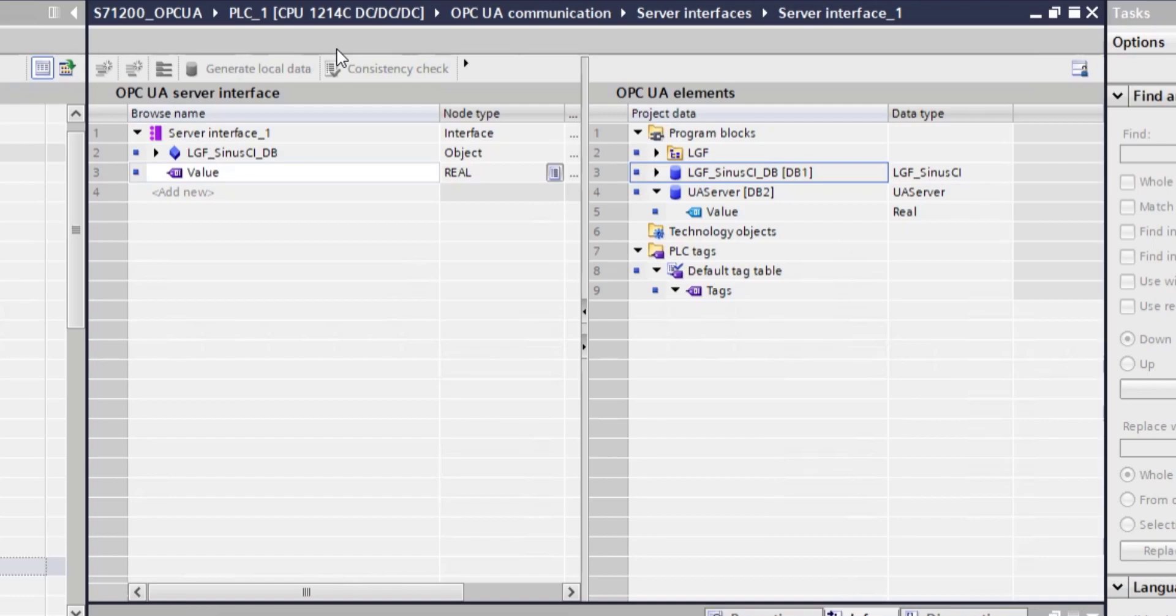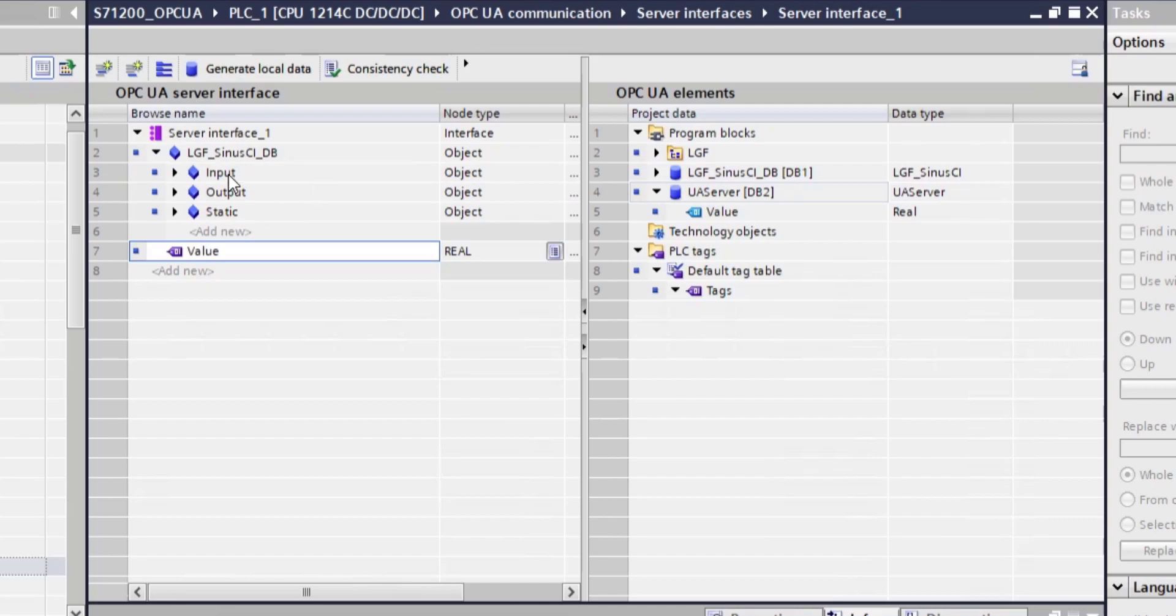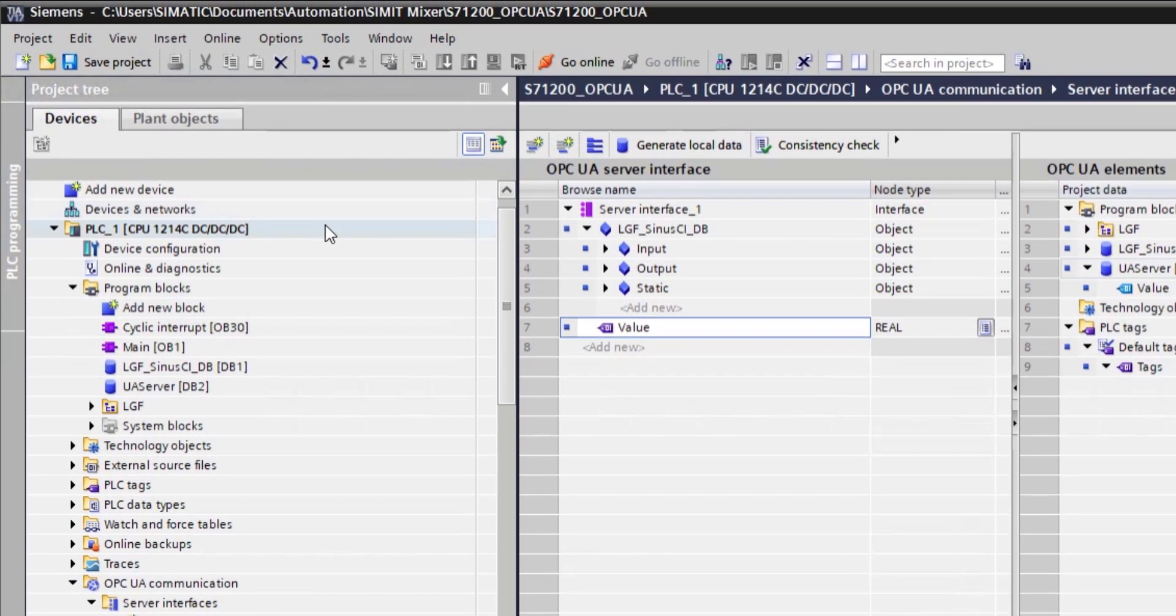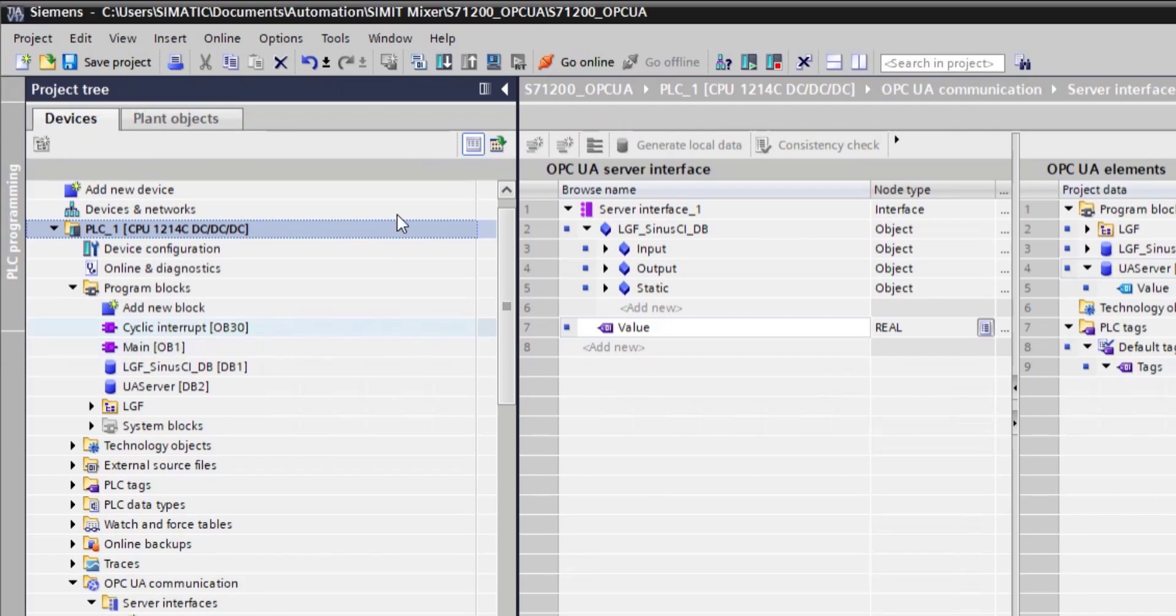You shouldn't be exposing everything on the PLC. You should only expose the data that is relevant and that is required to be exposed to some other systems that can access it via OPC UA. So currently, we are exposing the value from the UA server data block and we are exposing entire LGF instance data block here. So let's see what happens now. Let's download this to the device.